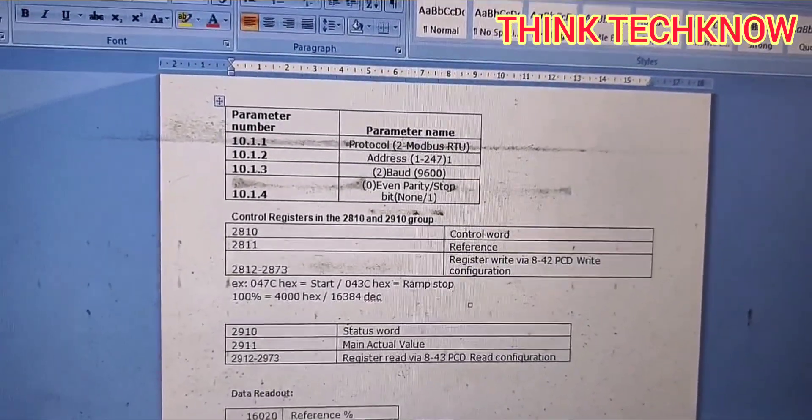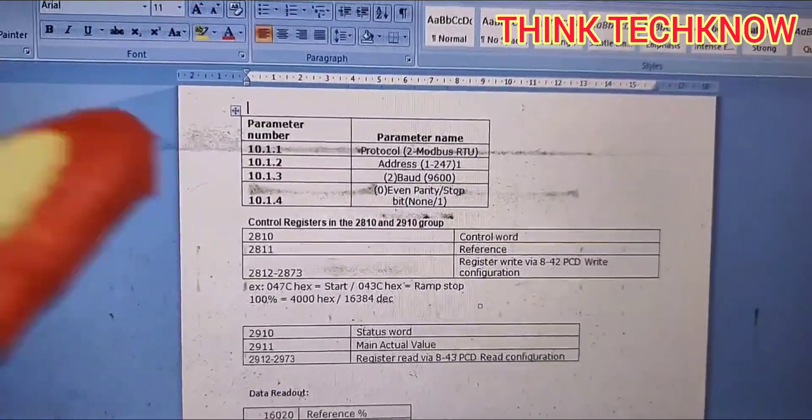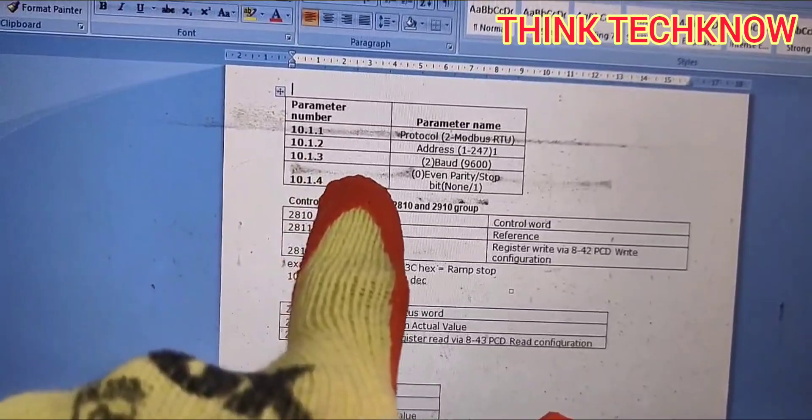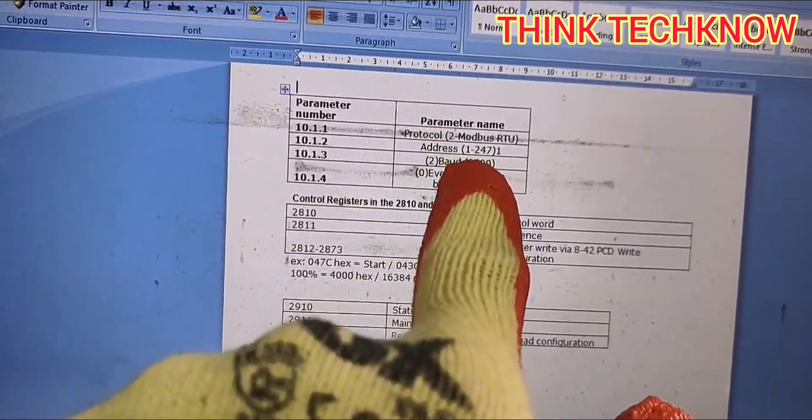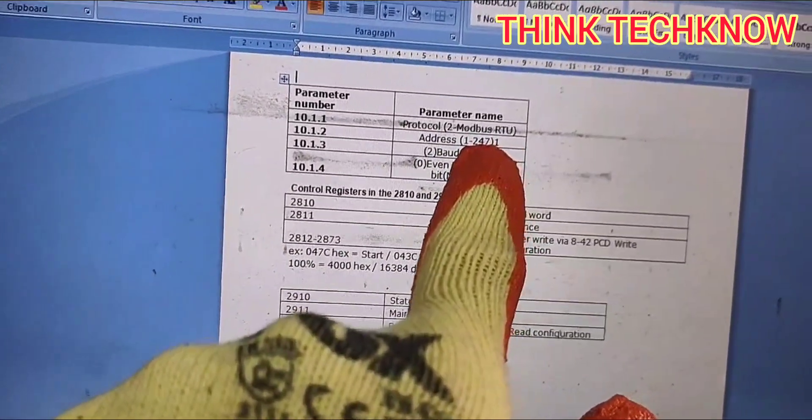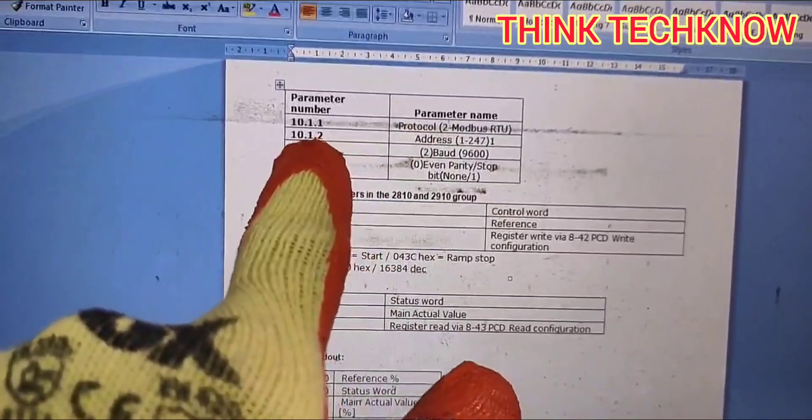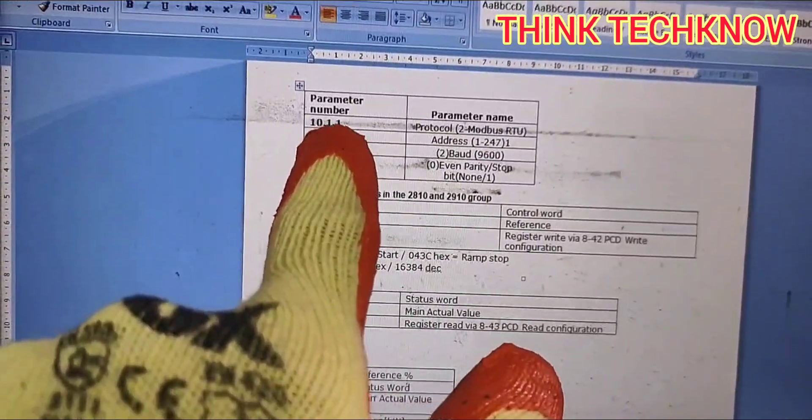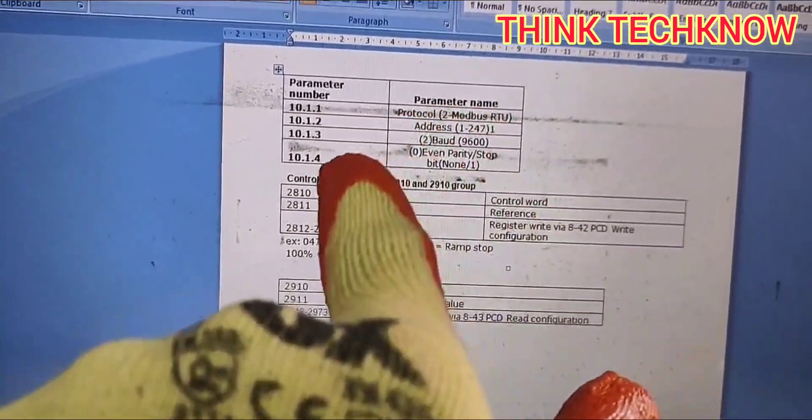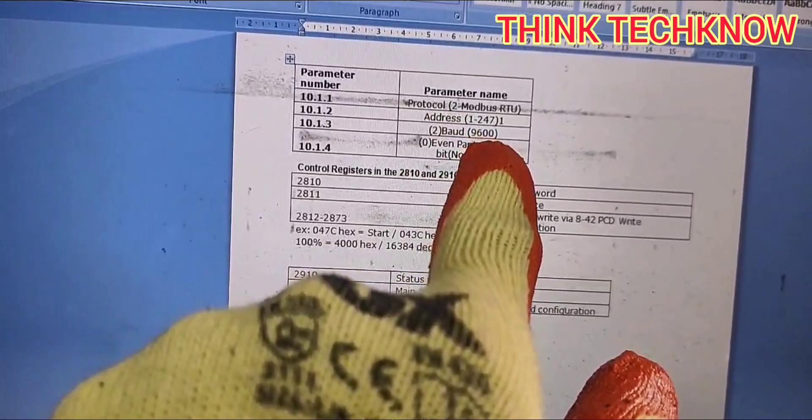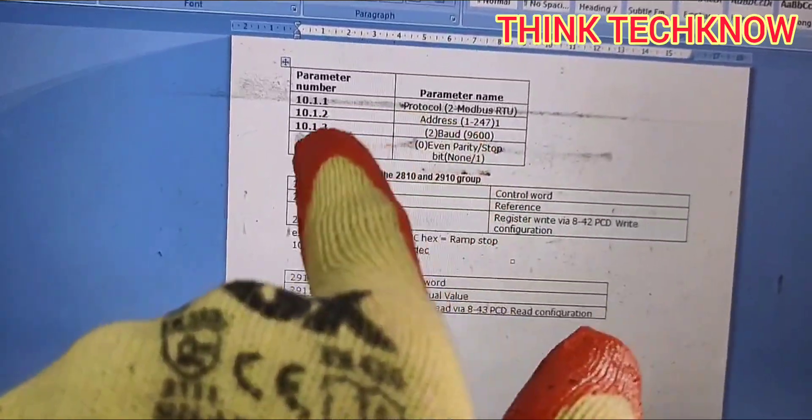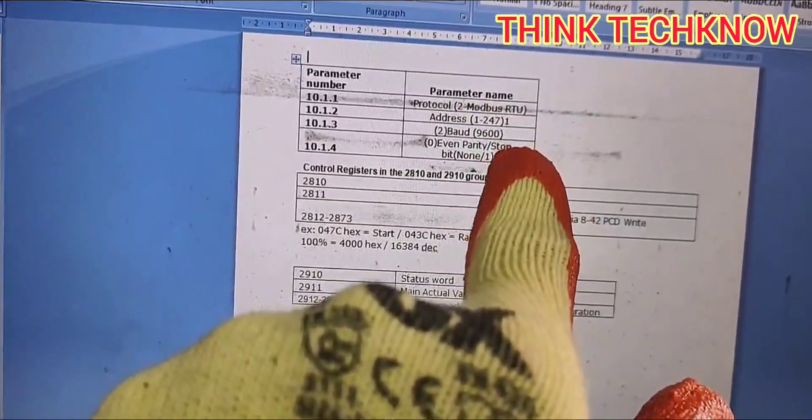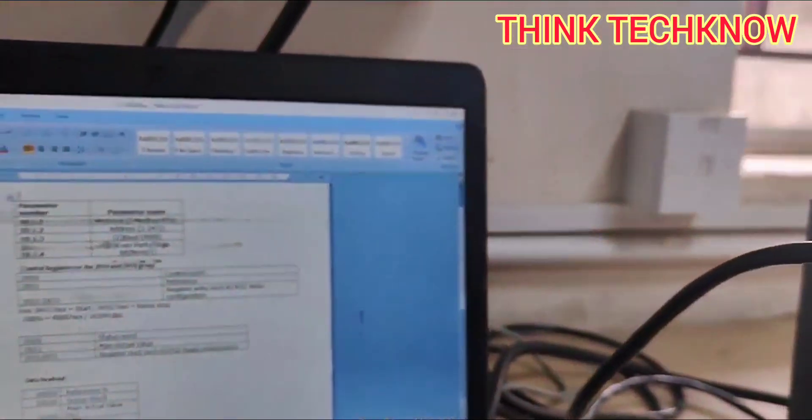This is the parameter list you can see on the screen. You can pause the screen and note your own value. At 10.1.1, you need to enter the Modbus RTU protocol. At 10.1.2, you need to select the address. At 10.1.3, you need to select the baud rate, and 10.1.4 is for parity.